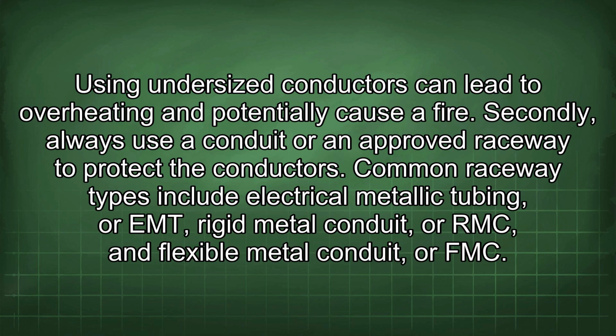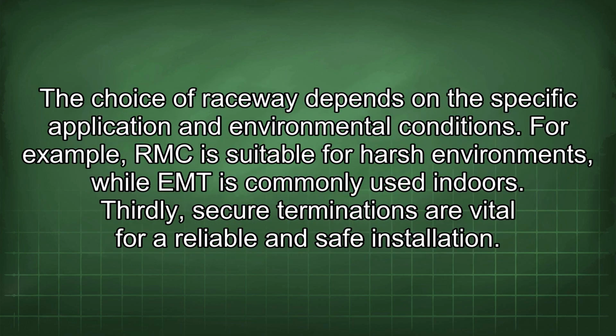Secondly, always use conduit or an approved raceway to protect the conductors. Common raceway types include electrical metallic tubing, or EMT, rigid metal conduit, or RMC, and flexible metal conduit, or FMC. The choice of raceway depends on the specific application and environmental conditions. For example, RMC is suitable for harsh environments, while EMT is commonly used indoors.